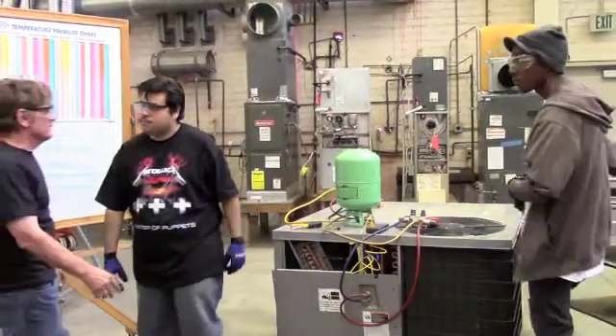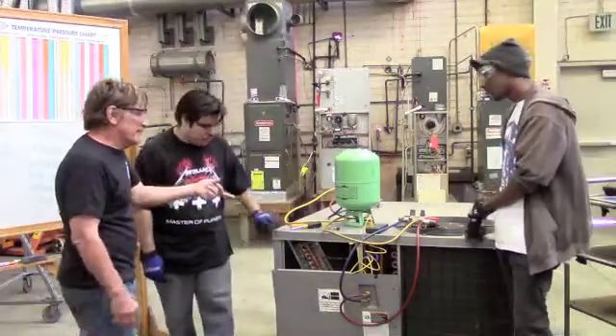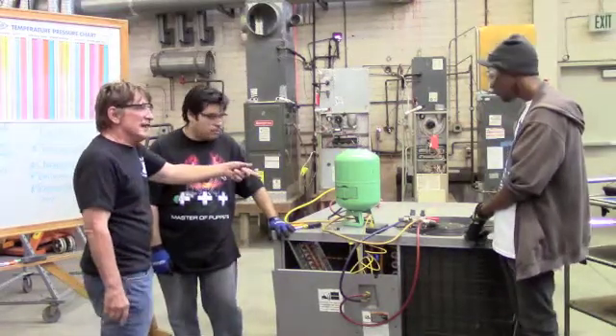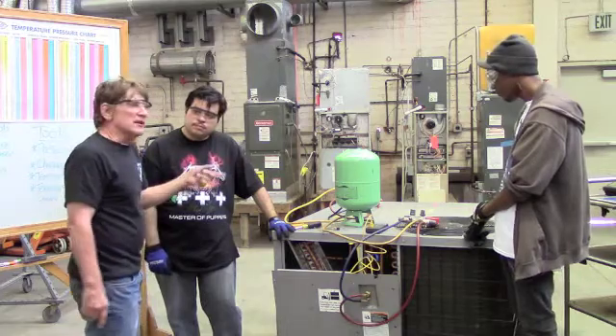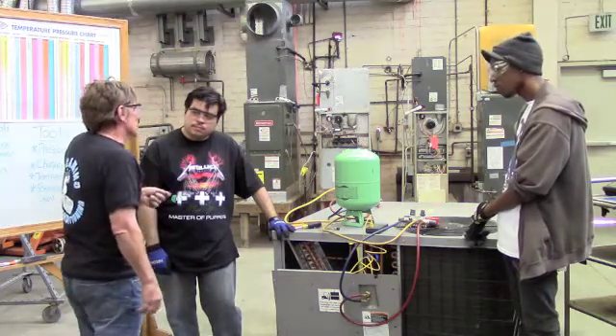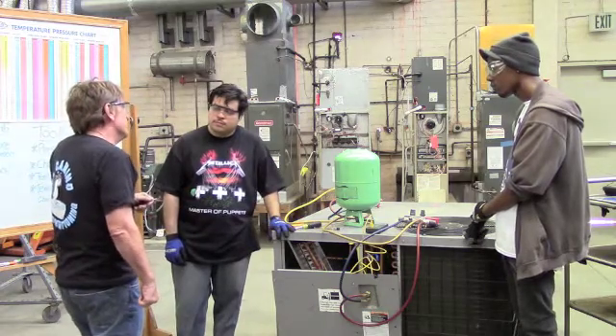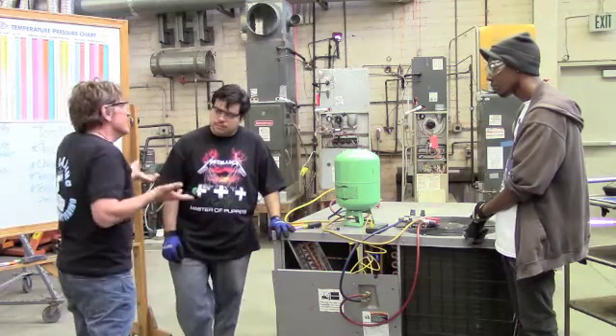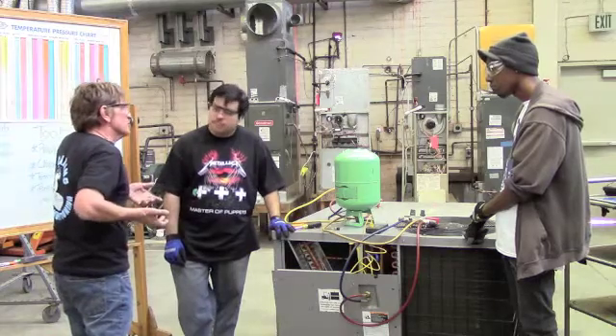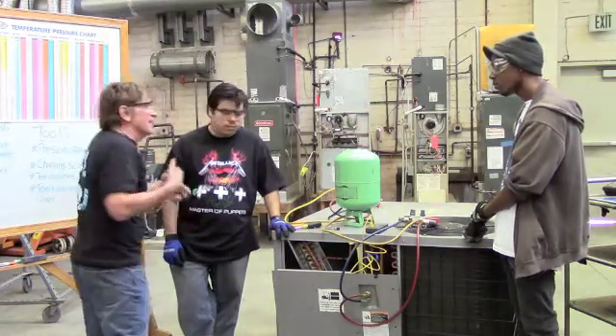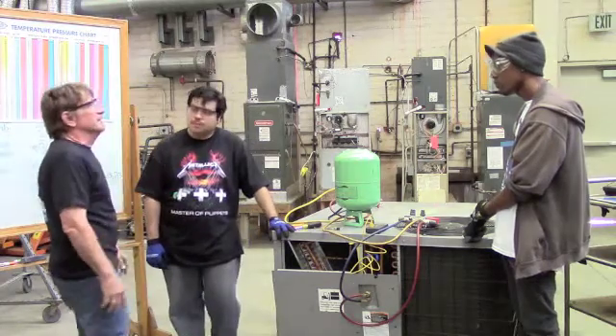That sounds pretty cool. So, I clamped on temperature probe to my suction line. And then I took the gauges and I converted my suction pressure to temperature. And that actually gave me the superheat that I was supposed to have. It actually even told me to either add refrigerant or remove refrigerant. Now, obviously, I can't just vent that refrigerant out, right? I've got to recover it again, right? And all these rules.